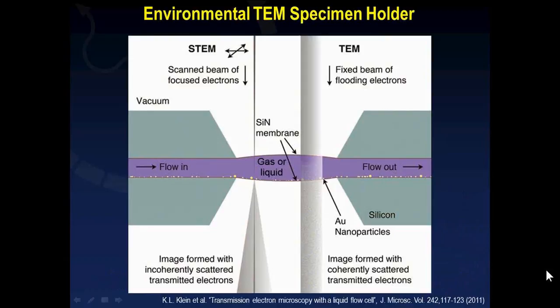The schematic of a specialized environmental TEM holder consists of a pair of electron-transparent windows above and below the specimen. The specimen is usually dispersed on a membrane inside the sandwich window, within which one can introduce gas or liquid. The windows isolate the liquid or gas environment from the high vacuum of the transmission electron microscope.